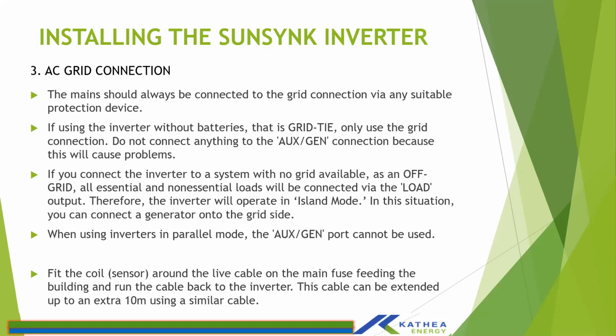You can actually set the times. We'll look into it when you're on the commissioning slide tomorrow. You can control the aux port to give an output for ATS. You can set it to give an output, let's say when the battery goes to 20%, and then that output starts up your generator, and then you use the generator to charge up the batteries. We'll cover how you set it up in our session tomorrow, but it's possible to use your generator when the battery goes low, and then the ATS will give an output to the generator.